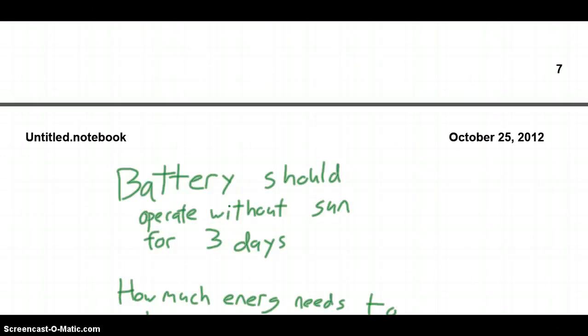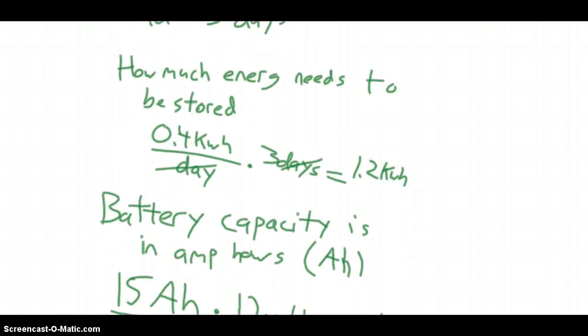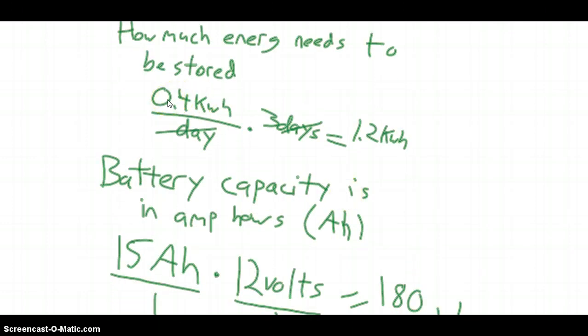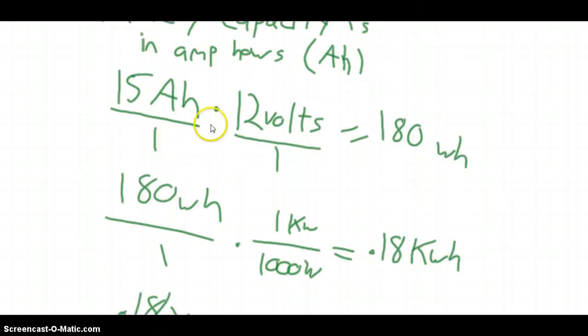So, the big thing with batteries is you need to choose how long they should be autonomous, which means how long they should operate without sunlight. So this is going to depend on your climate, but we assume 3 days. And then we need to figure out how much energy needs to be stored to power our light bulb for 3 days without any sunlight. So in this case, we need to store 1.2 kilowatt hours. What's weird about batteries, though, is that battery capacity is measured in amp hours. So we have to somehow figure out how many kilowatt hours are in one of our batteries. So we assume one of our batteries is 15 amp hours.